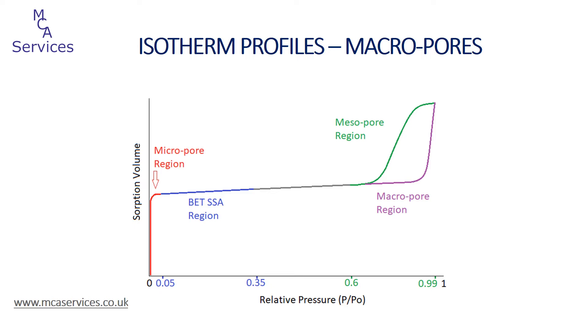This imposes a maximum pore size limit to which the isotherm can be used to resolve the pore size distribution. This is often poorly defined and rather dependent on the shape of the isotherm and, more importantly, the highest measured relative pressure for our choice of adsorbate and analysis temperature. For nitrogen at liquid nitrogen temperatures, the limit is typically around 200 nanometers.